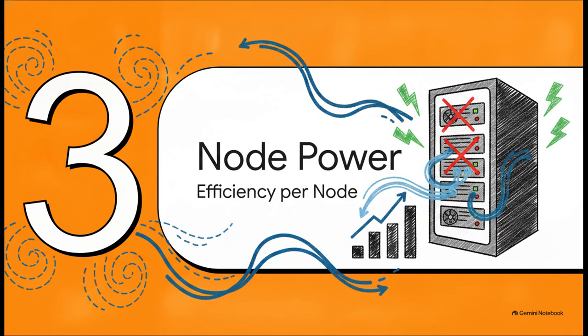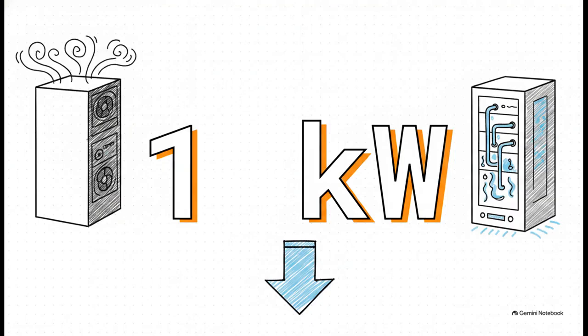Moving to Section 3, node-level power savings. Zooming in closely on a single server node, it really comes down to one crucial number: 1 kilowatt. During actual production workloads, the average power drawn by the air-cooled node was 6.2 kilowatts, but the liquid-cooled node drew just 5.2 kilowatts - a consistent, massive 16% power reduction right at the node level.